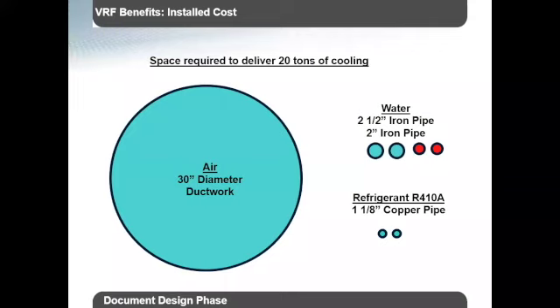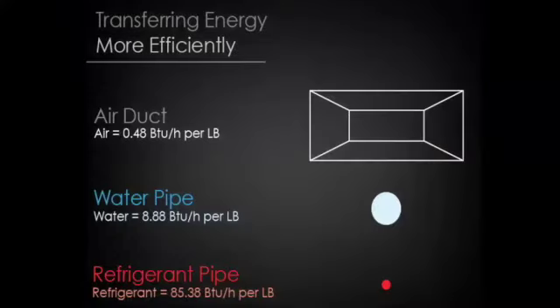And even once we look at the ductwork again, I want to stress that, as you guys are watching it on your computers, it is not life size, but it is to scale. So this gives a pretty valid representation of the size difference between your air ductwork, your water piping on a 4-pipe hydronic system, and your 2 pipes coming from your VRF system. Now, it seems counterintuitive that you can provide that same 20 tons of cooling or heating to a space with such a small amount of piping as opposed to the larger piping on the hydronic system, and also the very large ductwork coming in off of your typical rooftop unit. And we're going to look at how that's actually possible.